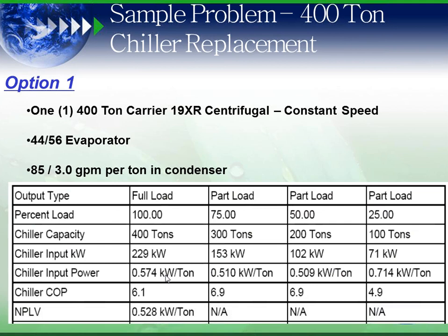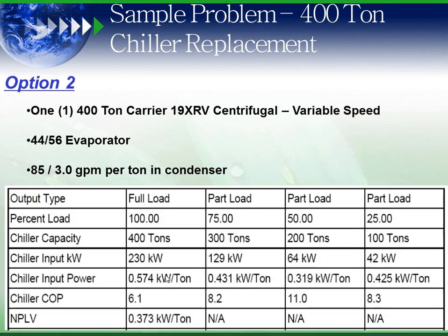Option 1, let's look at a 400-ton Carrier 19XR centrifugal constant speed machine. I'm running it at 0.574 full load, 0.528 part load, the chiller itself. Option 2, a centrifugal with the variable speed drive, 0.574 full load, 0.373 part load.